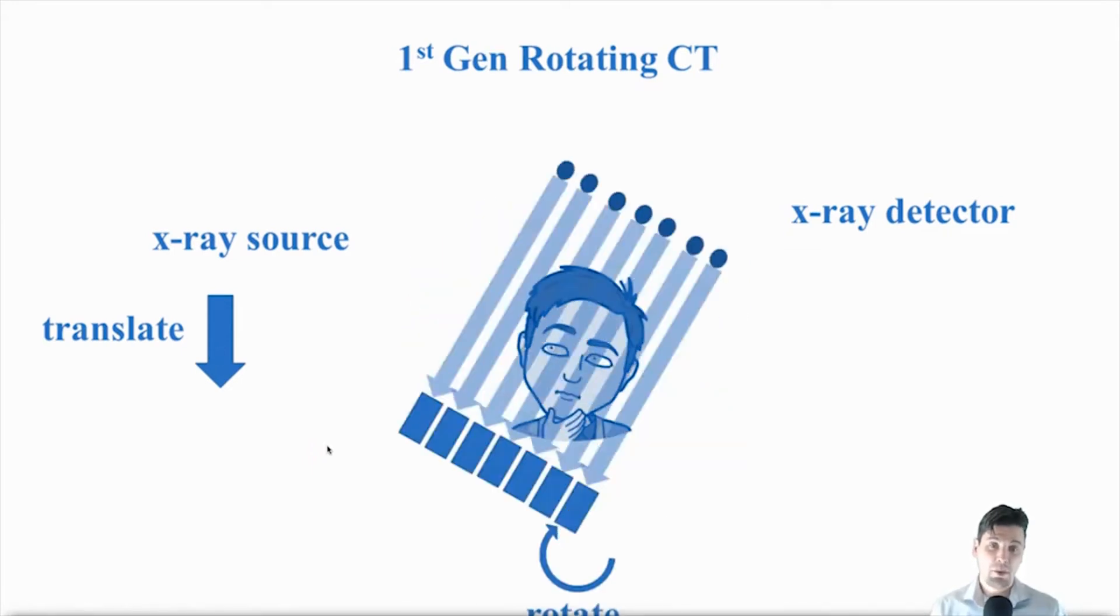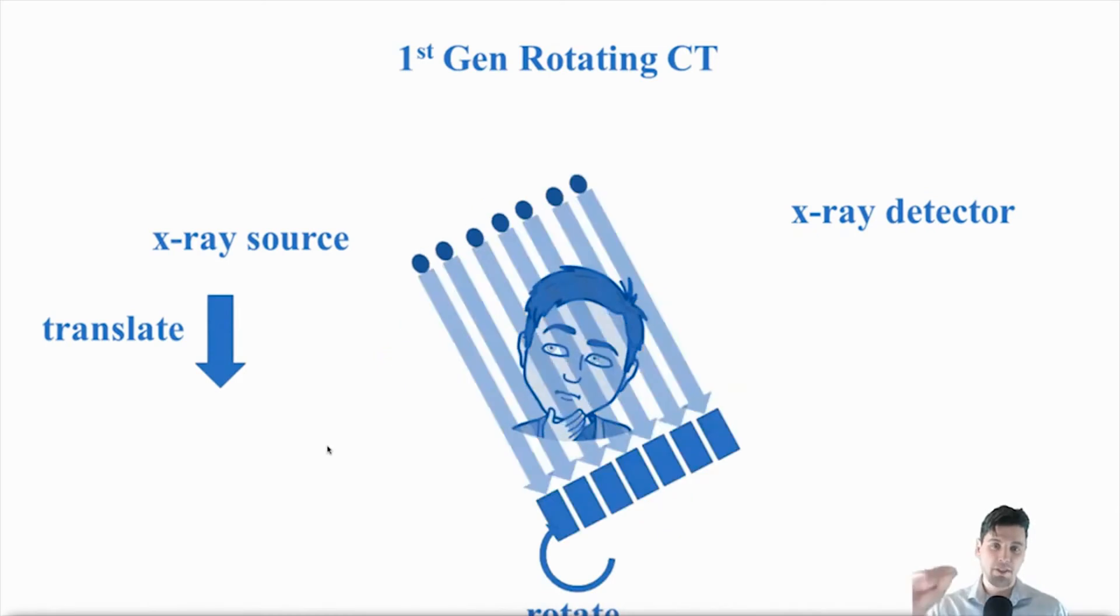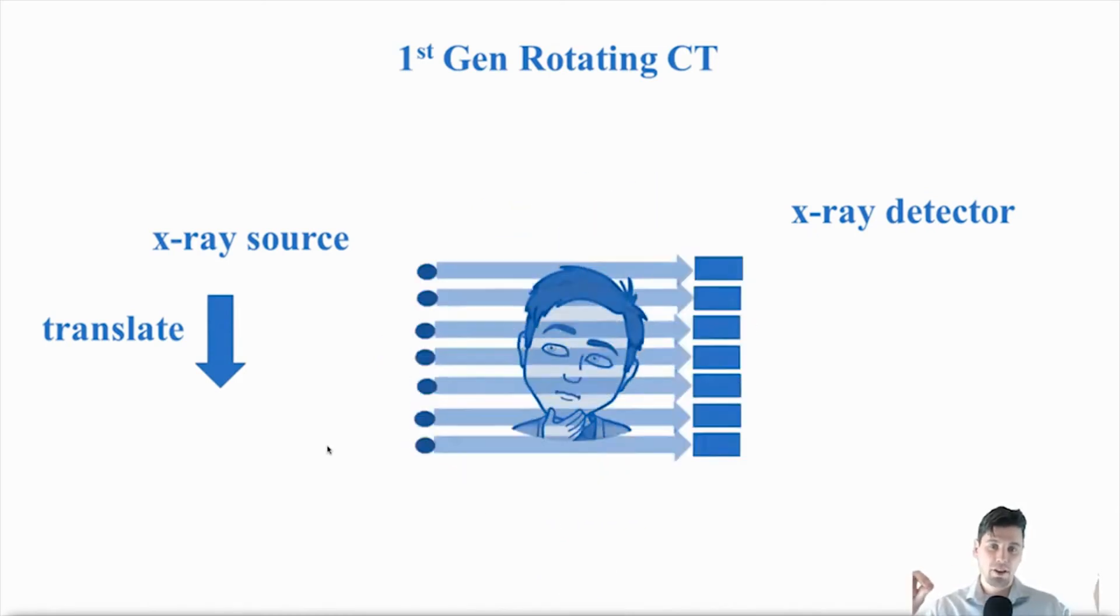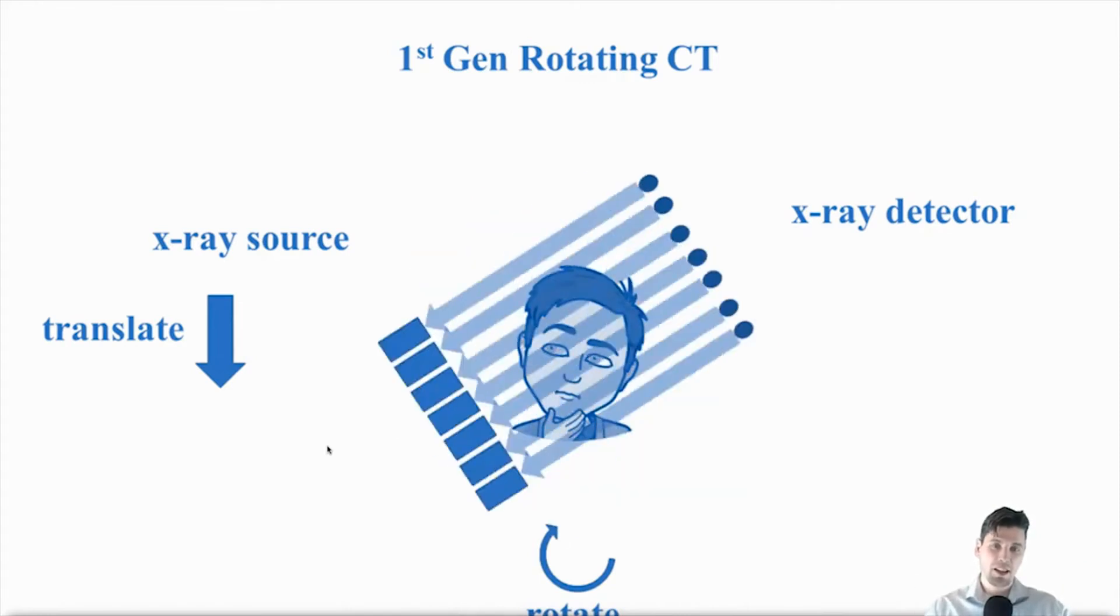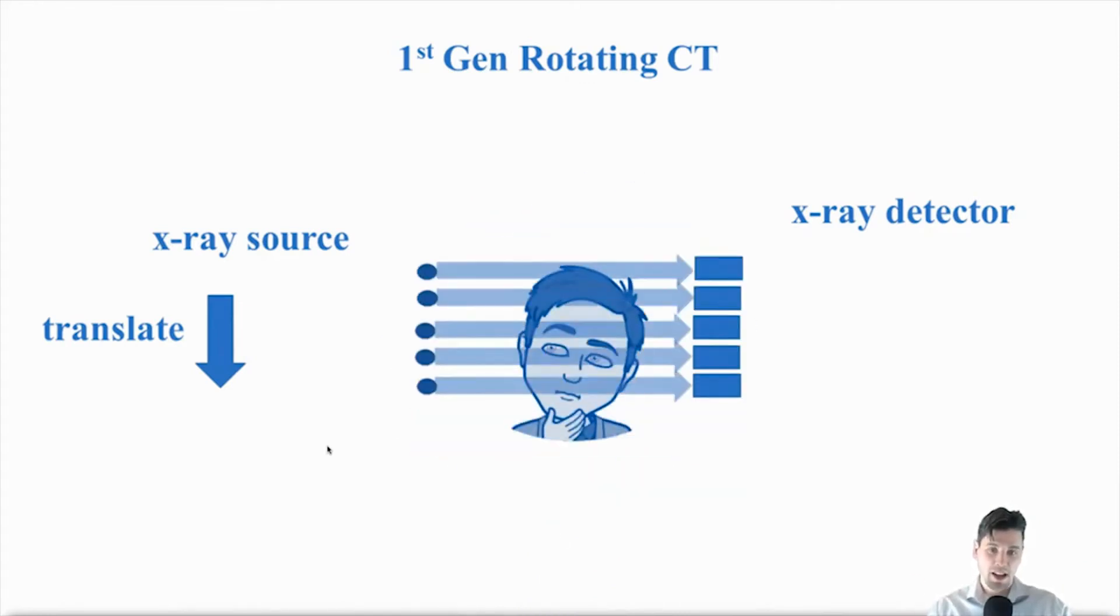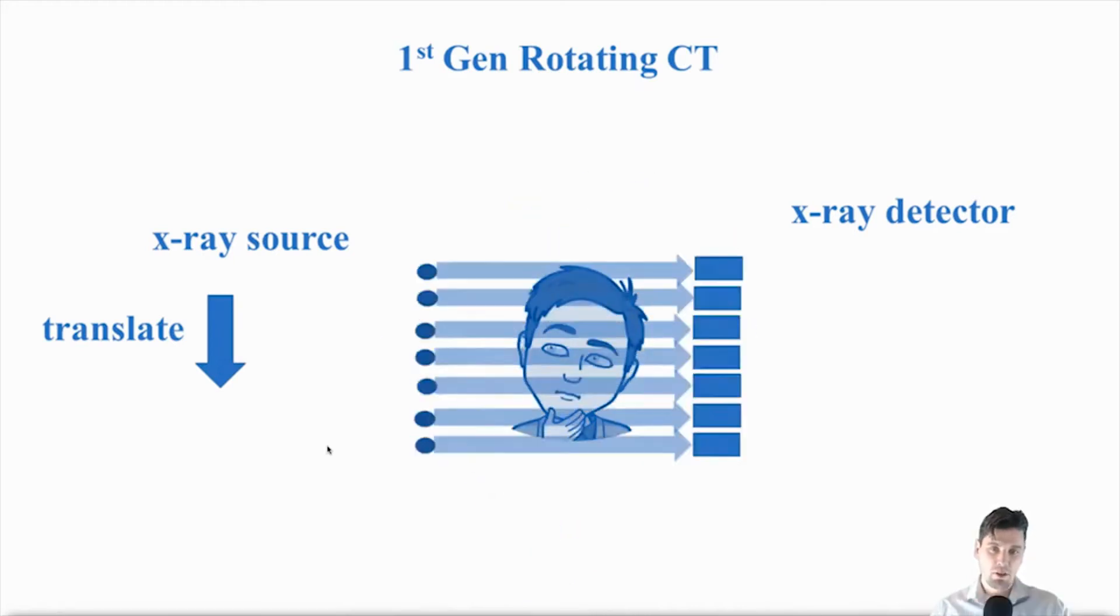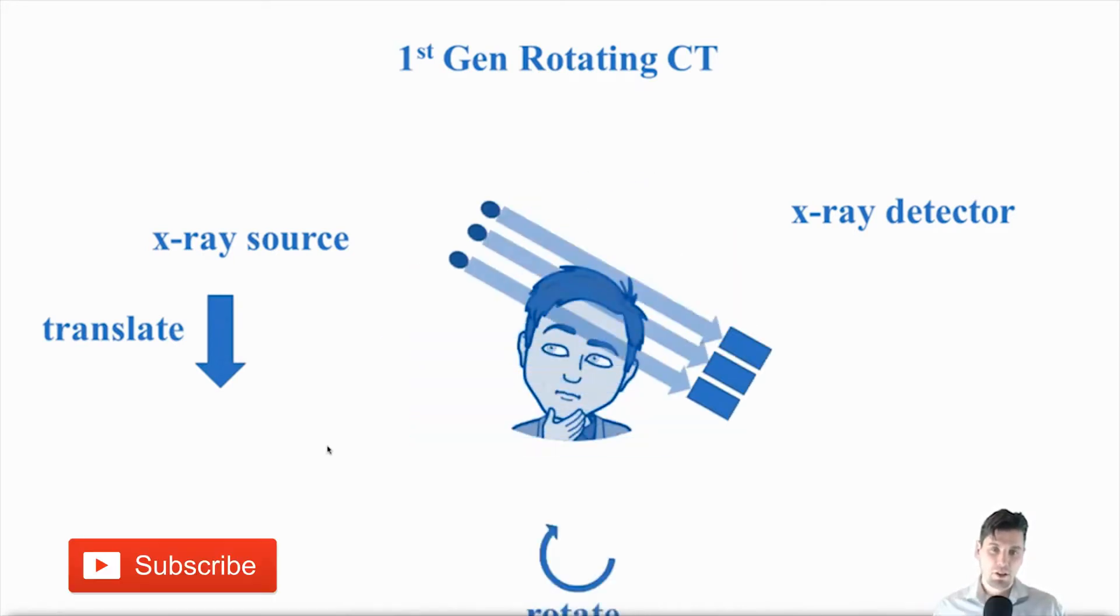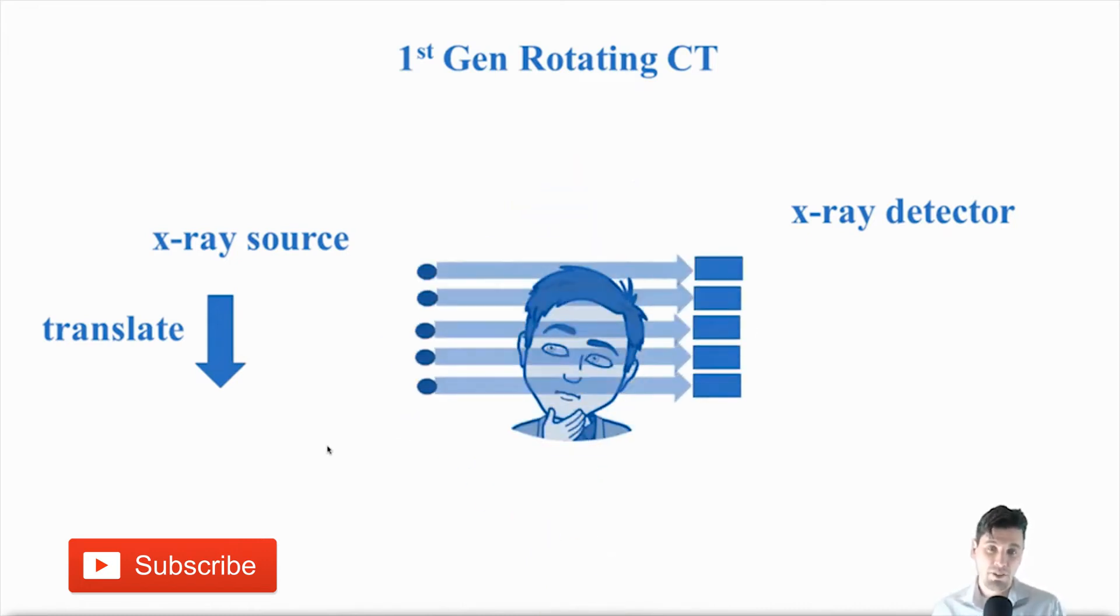So each time we wanted to acquire one view angle, we would have to have the x-ray source and the x-ray detector acquire one ray essentially through the object and then they would translate together. So the x-ray source again acquires one ray through the object, translates again one ray and keeps doing that and that would just give us one view.